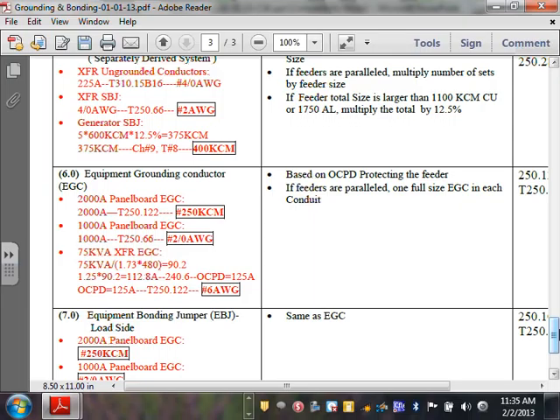So that's an equipment grounding conductor. But the assumption, guys, is that everybody understands the equipment grounding conductor, the grounding electrode conductor, the main bonding jumper, and the system bonding jumper. That bigger terminology, guys, you kind of have to know it. This is just fitting everything together. Hold up right there. On that number 6 for the 1,000, that table there should say 250.122, not 66.